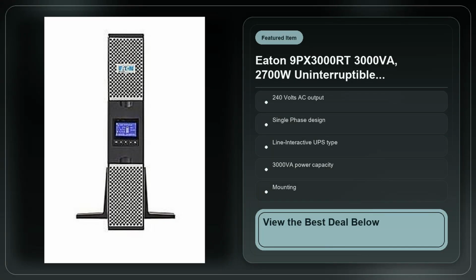If you're planning to run the UPS at 80% or higher load for extended periods, the runtime shrinks dramatically, and you'll feel that when you try to power a server farm at peak usage. So the 9PX is a brilliant protector when you size it correctly, matching the load to about 30-50% of its rating, but it can become a disappointment if you overload it.